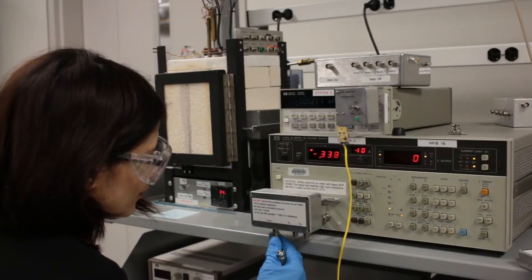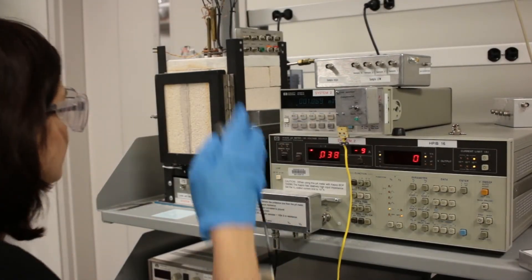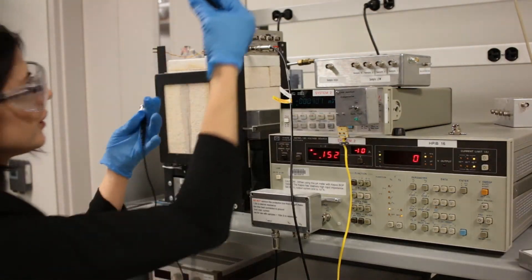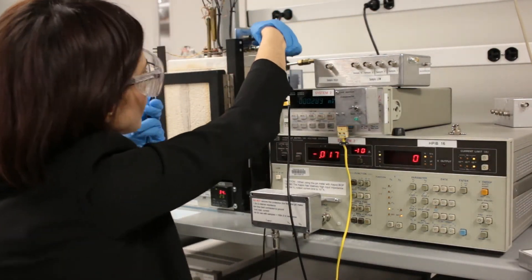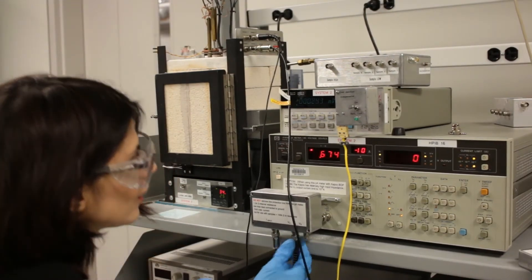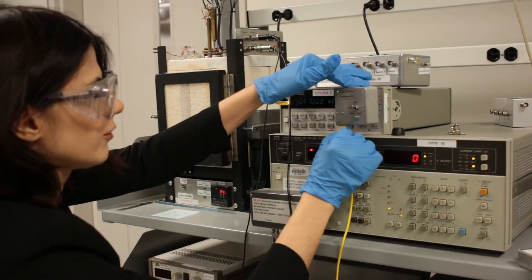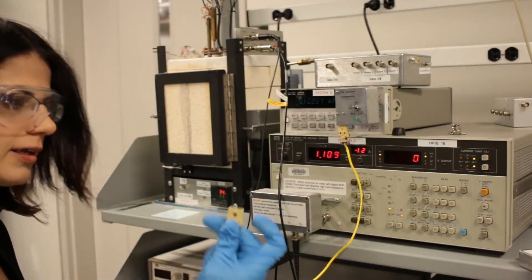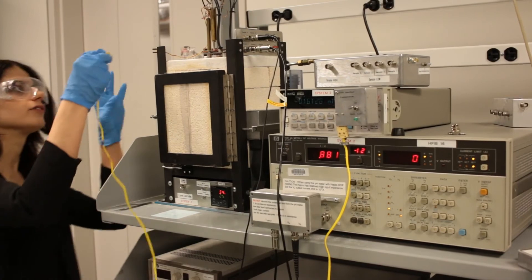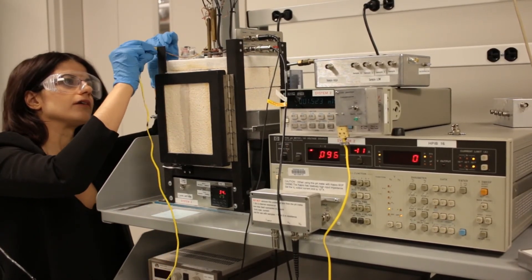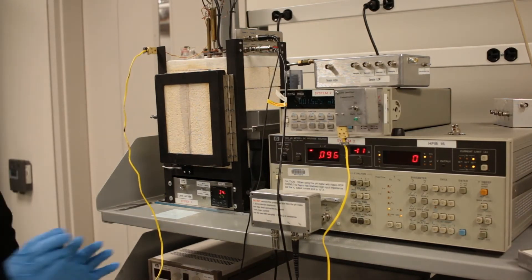Electrical connections from sample to picoammeter are achieved by using BNC and triaxial cables. Here, we are trying to measure ultra-low currents in the picoamp current range. Therefore, we use triaxial cables to minimize leakage current arising from the cable itself. Using triaxial cables instead of BNC counterparts becomes extremely important for TSDC measurement of pyroelectric samples due to the contribution of pyroelectric current to the thermal relaxation current.